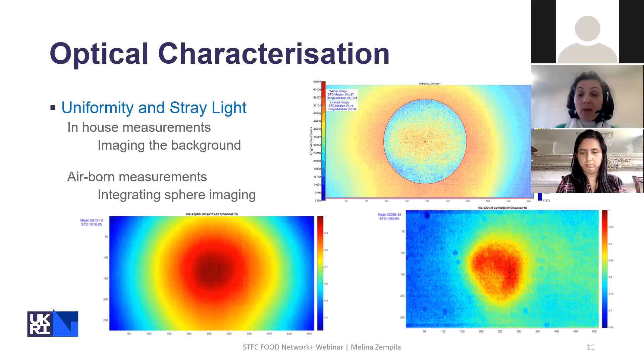For the linearity test, one can try several combinations of settings in front of our integrating sphere, but you can also test the linearity of the channels by using our reflectance calibration targets. Either way, the procedure is relatively simple and very beneficial, because not only do you have an overview of what is happening with your sensor, but you can assess its linearity and make corrections if you need to.